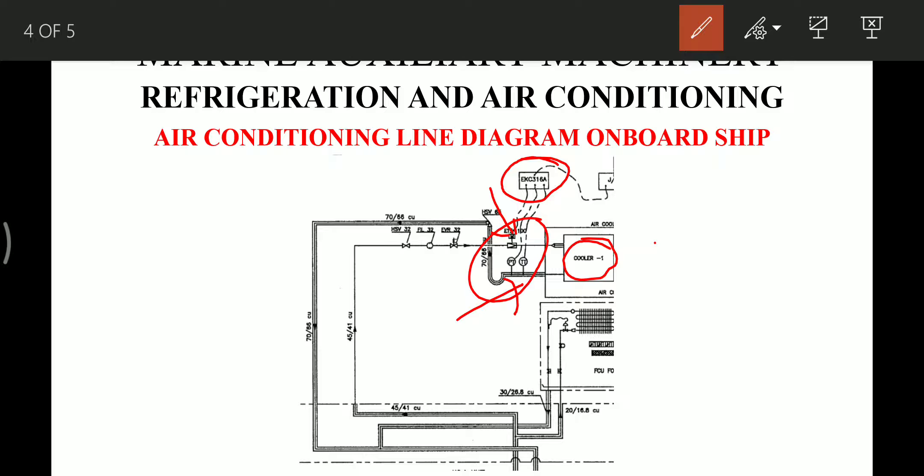There is also a solenoid valve, which is operated by the thermostat placed in the evaporator coil. When the set temperature is reached, this solenoid valve closes. The closing of the solenoid valve causes a low pressure condition that activates a cutout on the compressor and stops the system. There is also a manual valve provided to isolate and perform maintenance on the cooler.